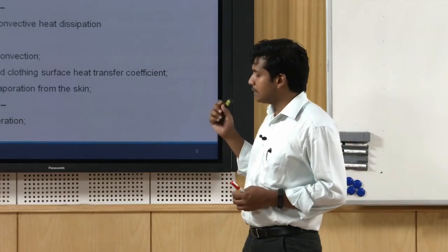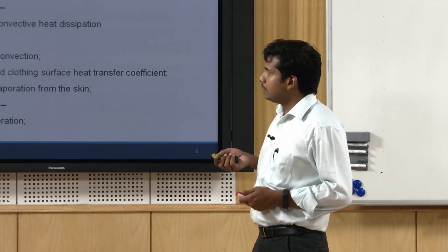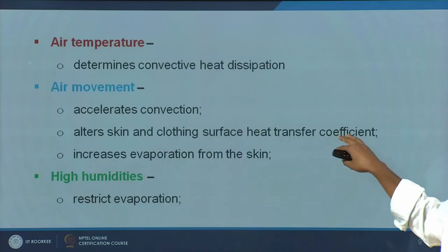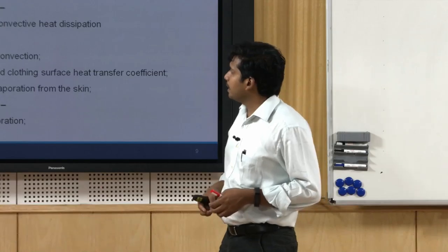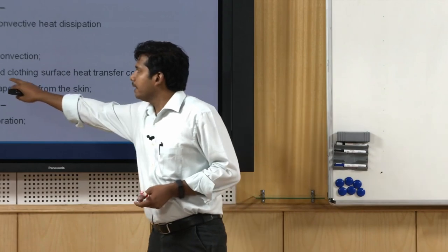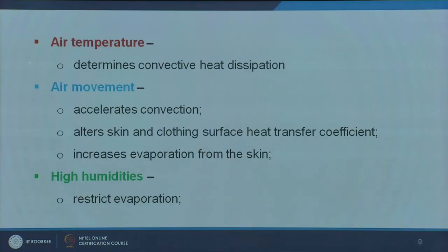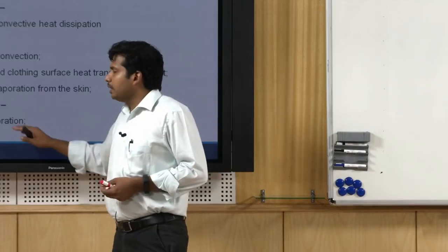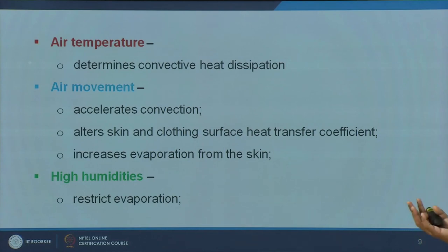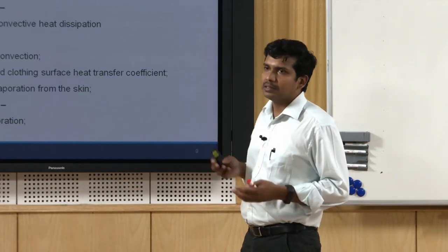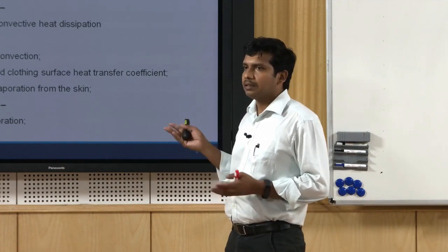Air temperature determines the convective heat dissipation — how effective convective heat losses or gains happen is determined by air temperature. Air movement accelerates convection, alters the skin and clothing surface heat transfer coefficient, and increases evaporation from skin — higher velocity means better heat losses during summer. When humidity is really high — 90 to 95 percent — it restricts the amount of evaporation that can happen, so you start feeling more uncomfortable. This is typically what happens in coastal areas or humid climates.